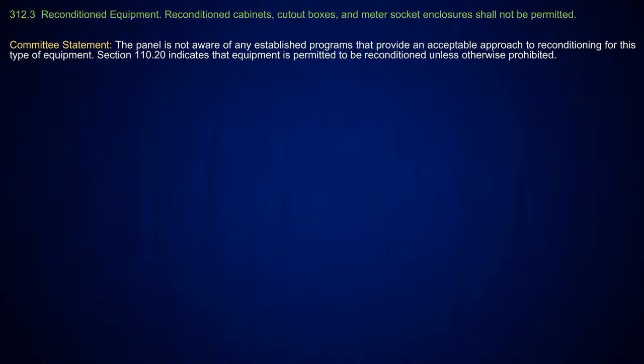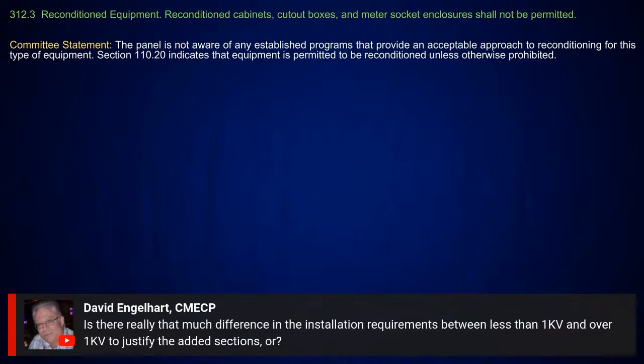And that is one of the things I've been talking about. When you go in and look at these different things, when I get to Article 314, it says you can't recondition an outlet. It doesn't say outlet points. And like I've been trying to say, a point is established somewhere. You've got to have something there. So I think this is going to be very important just to take care of this.